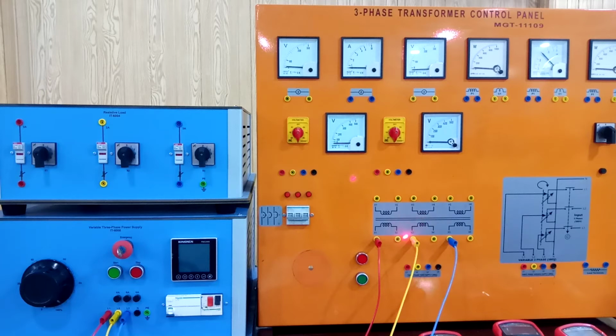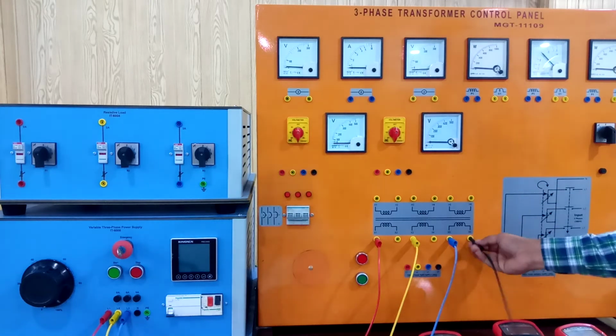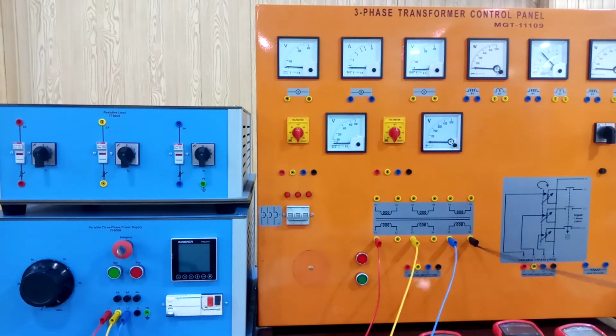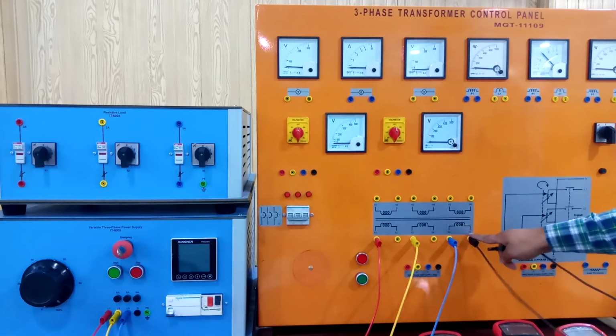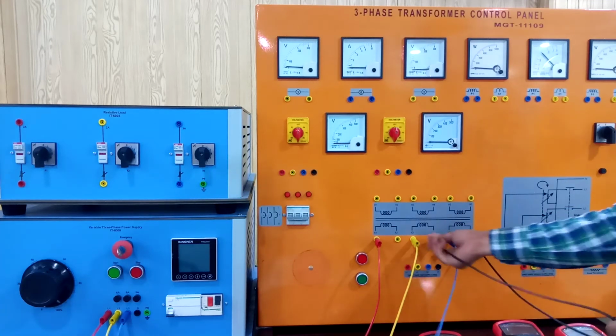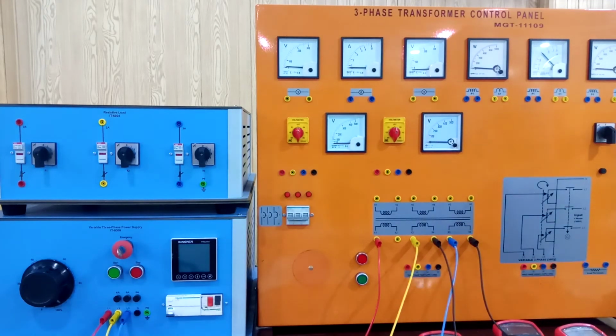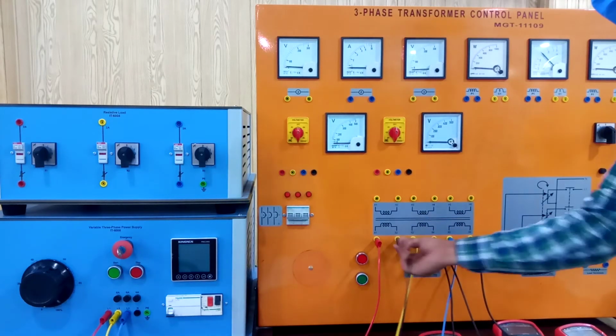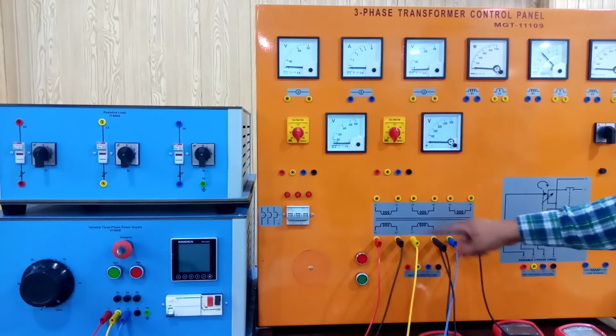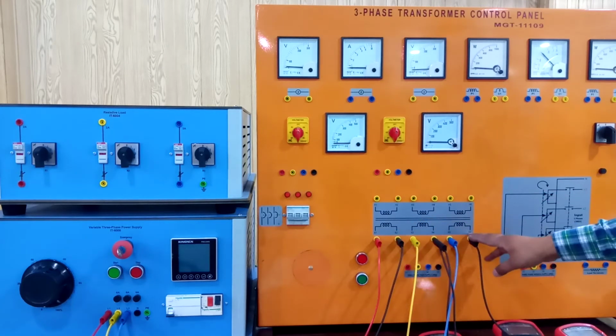Now it's time to connect the neutral. The neutrals will be common over here, so I will be making multiple connections. This is the way I'm going to connect the neutral of the third transformer, x6, to x4, and then x4 to x2. This is how you connect the three transformers in common.